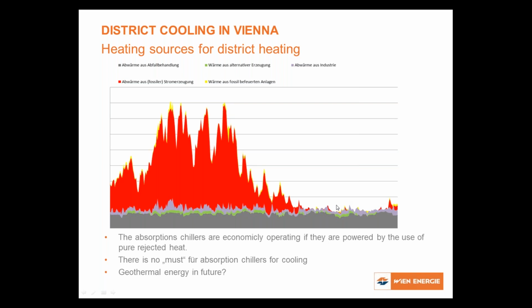So we are talking about summertime, when we have waste heat from the waste incineration all summer long, and this has to be used in some way. We use this heat in absorption chillers to power them. It's always a topic of prices - during summertime we have this waste heat, which makes sense to use. If you don't have waste heat, absorption chillers make hardly any sense in my opinion. So there's no must for absorption chillers, but if there is heating energy during summertime, it makes sense.